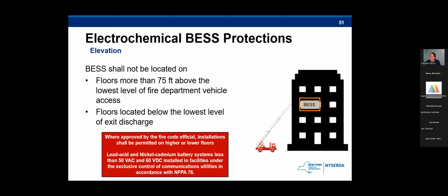So here we have the elevation requirement. The International Fire Code has used this language for many sections within the fire code. The system cannot be located higher than 75 feet above the lowest level of fire department vehicle access or on floors located below the lowest level of exit discharge. There are exceptions for each of these systems if approved by the fire code official, so they can be permitted to be on higher or lower floors based on that additional hazard mitigation analysis or the large scale fire testing. They can also be permitted in underground vaults if approved by the fire code official. And there are specific batteries, lead acid or nickel, for the communication utilities again, that don't have to meet these thresholds. So the fire department officials do have a right to permit higher, but only if they feel comfortable with the energy storage safety features and the fire protection systems that are involved.